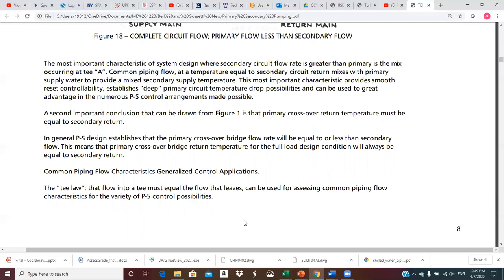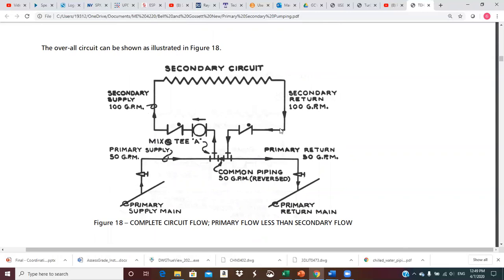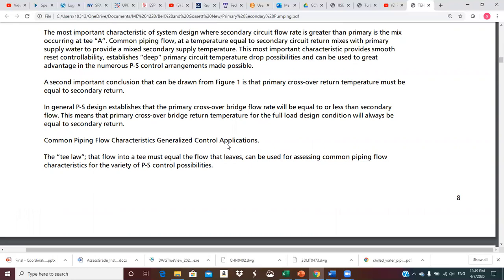A second important conclusion is that primary crossover return temperature must equal secondary return temperature. The 100 GPM return from the secondary is all the same temperature — it splits, with 50 going toward the primary return main and 50 recirculating through the common pipe. In general, primary-secondary design establishes that the primary crossover bridge flow rate will be equal to or less than the secondary flow, meaning primary crossover bridge return temperature at full load design condition will always equal secondary return temperature.